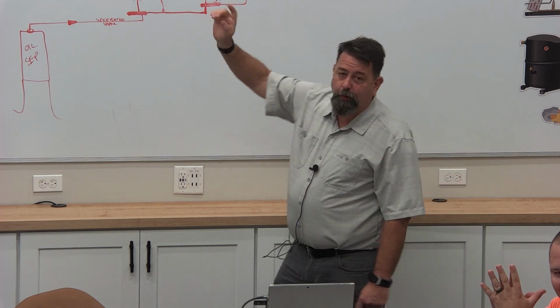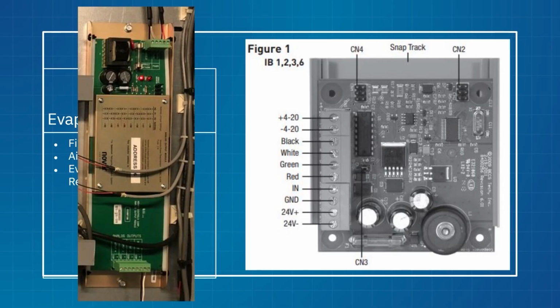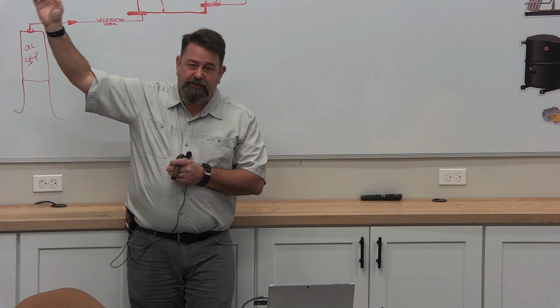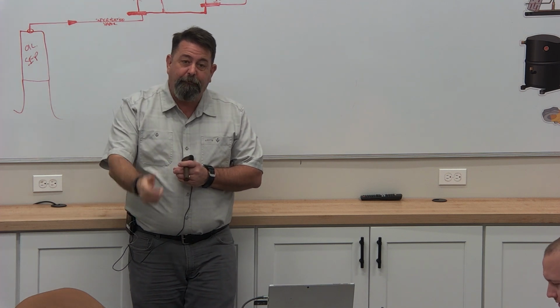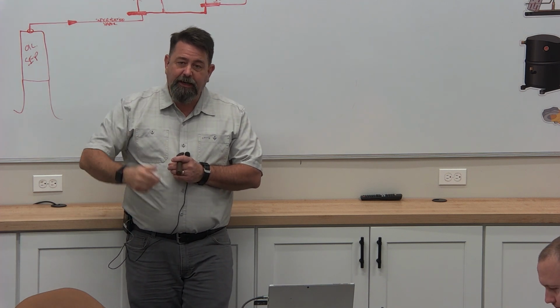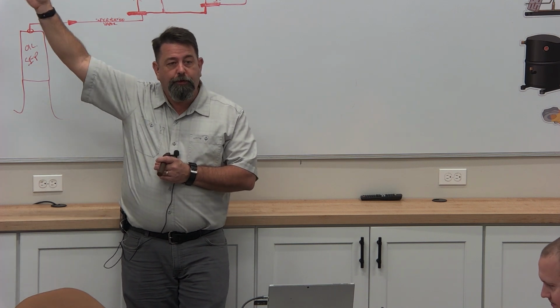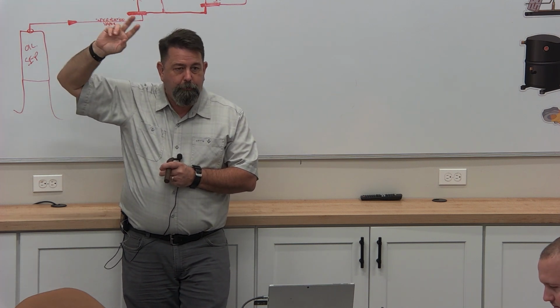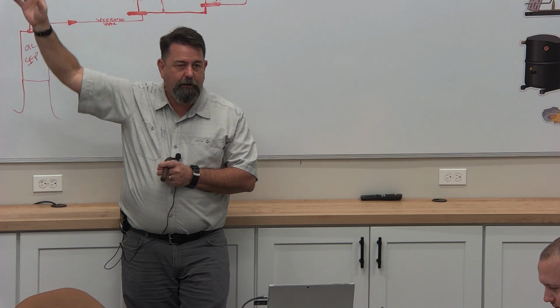But this is what we need to know as technicians - that board is specific to the step count. So if I replace this board, I've got to match the step counts of that board. If I change my valve and change the steps, that board will no longer work. Those are the two main things I need to know.